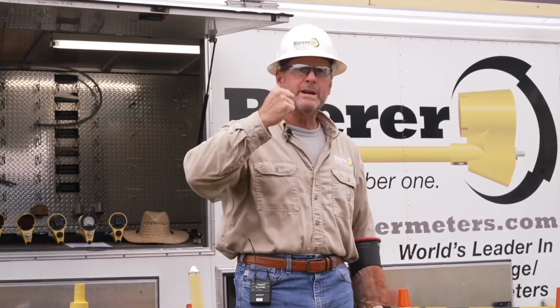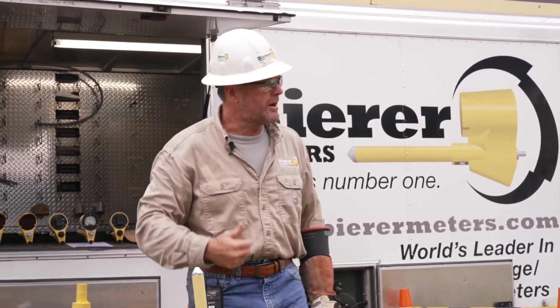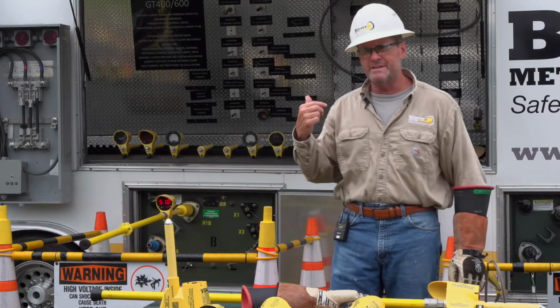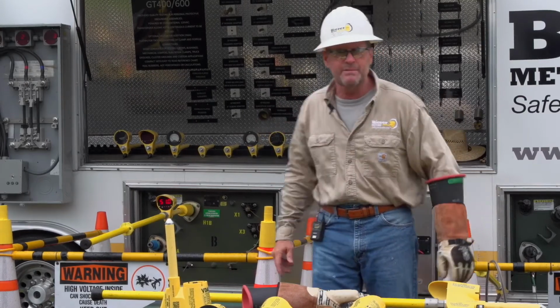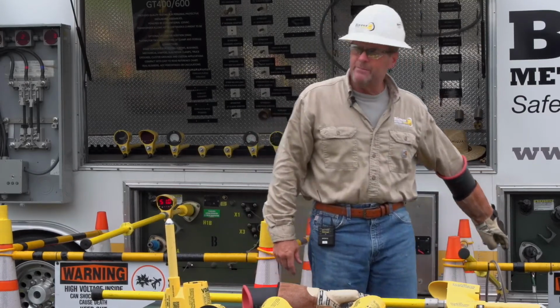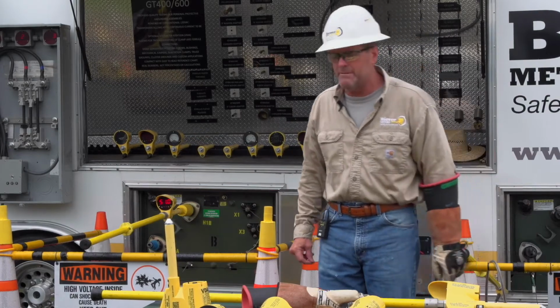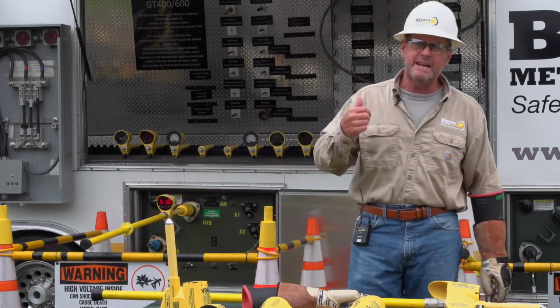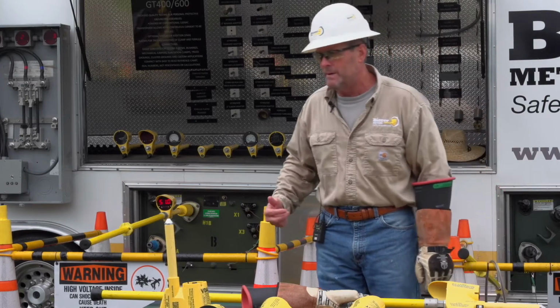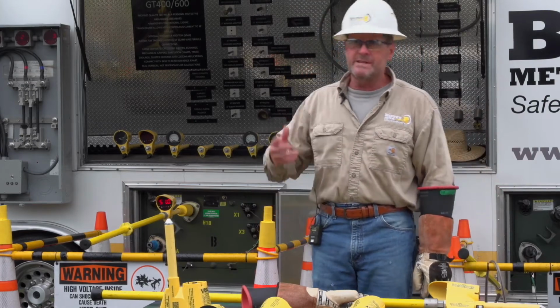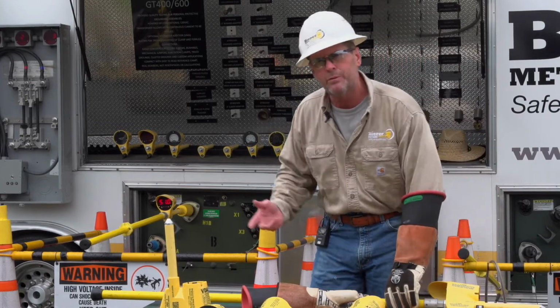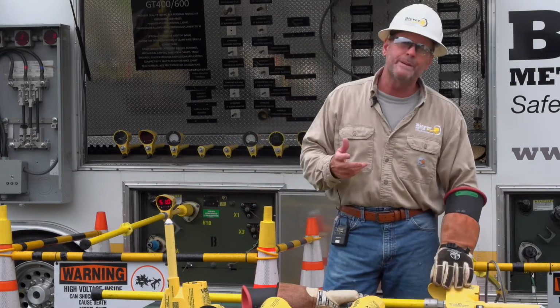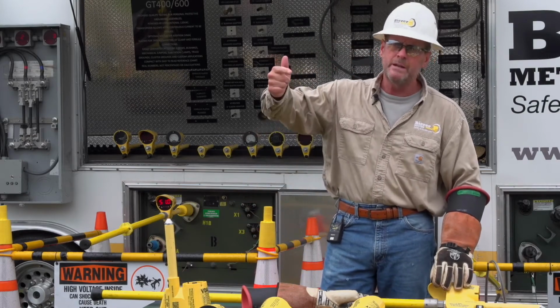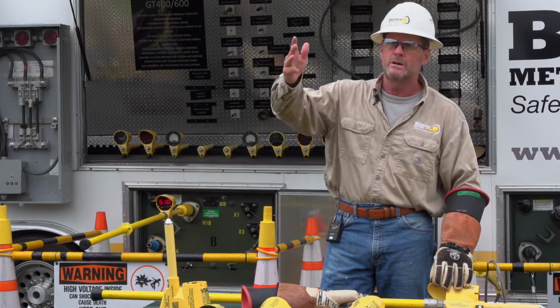When we go to safety classes or conferences, if we're doing a safety rodeo and this is one of the stations with a pad mount, and they ask us, hey, let's use your pad mount for one of the stations, open test ground on a pad mount — we say that's fine, we'll do it for you guys, but we're not going to do open, test, ground. We're going to do test, open, test, test the tester, ground. Five steps.